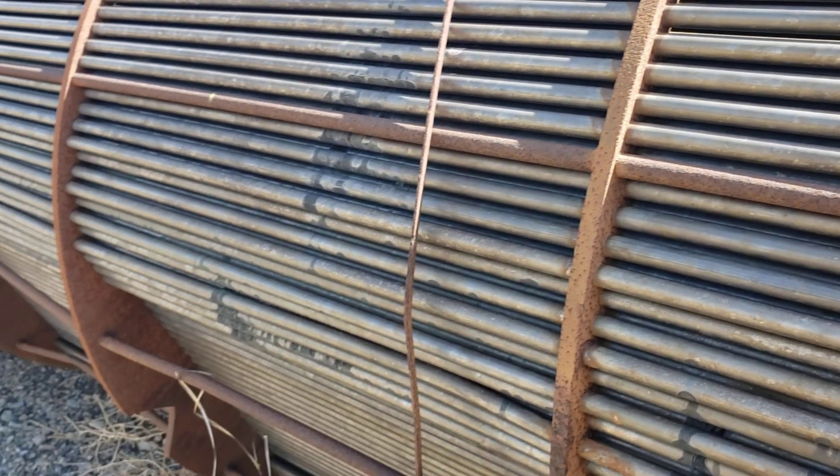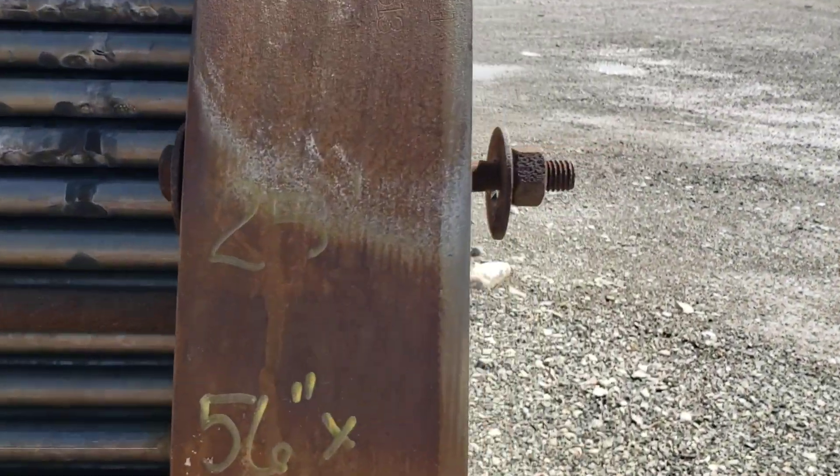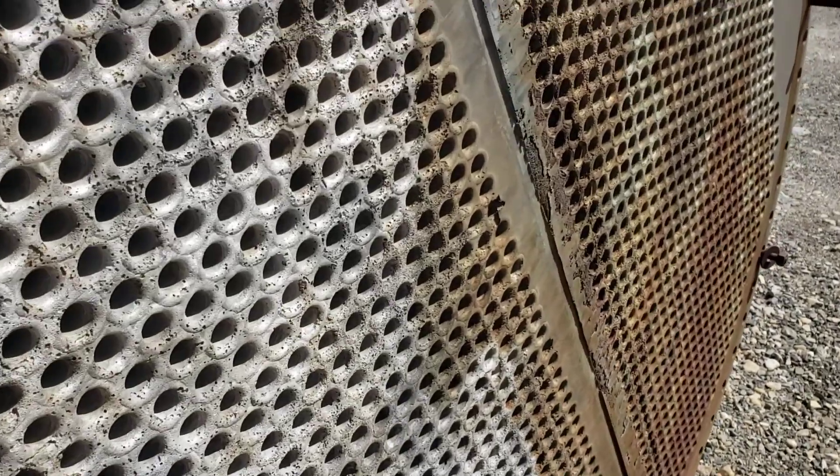This is what happens to bundles sometimes. Notice it's got carbon steel stay rods and baffles. They tried to build it as cheap as possible and got their money's worth out of it in that it got a run.